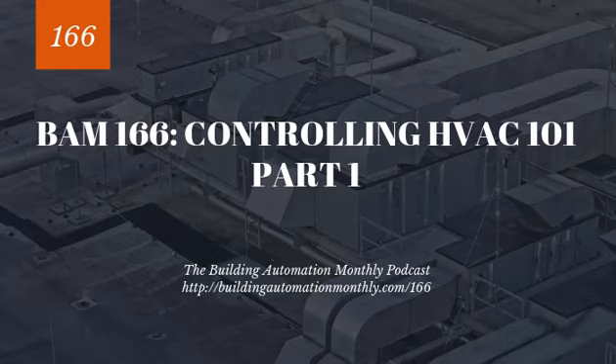And that is volumetric matching and volumetric offset. So in the case of volumetric matching, you have these spaces, and don't worry, we're going to get into VAVs and how all this works, but I'm just laying out a bunch of concepts for you right now. But in the case of volumetric matching, you match the amount of air going in and the amount of air going out, and you're basically trying to establish a neutral pressure in that space.